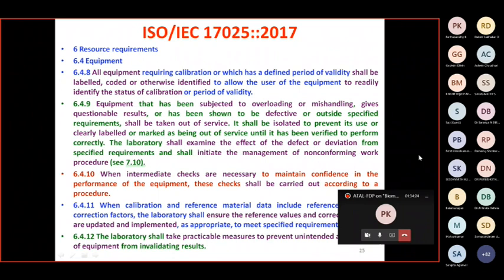So this you are familiar with. Any equipment or instrument which requires calibration should indicate the status on its face itself. If it is an instrument, put a sticker. If it is equipment, put a label or something hung on it in a prominent location, so that when you want to use it, just by looking at the tag or the label, you will come to know, yes, it has a valid calibration status. Then you can put it into use. You can also look at the calibration chart, but every time going into the computer or going to one location and seeing the calibration status may not be practicable. But putting a label or a sticker is easy to do.